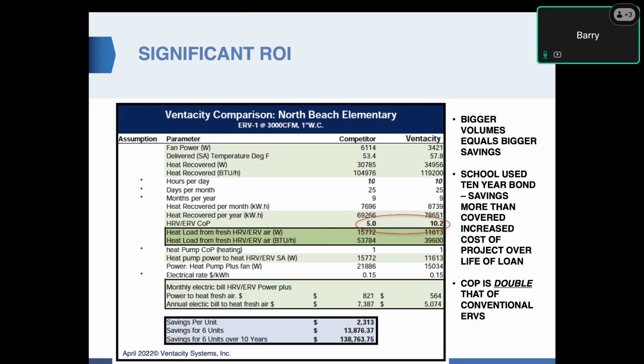The fan power for conventional HRVs was over 6,000 watts. For the very high efficiency, we were at 3,400, almost half as much power consumption. And then the heat recovered per month, you look at the difference there, and it's a fairly, not huge, but significant enough difference. What that translated into was a COP of 5 versus a COP of 10.2.